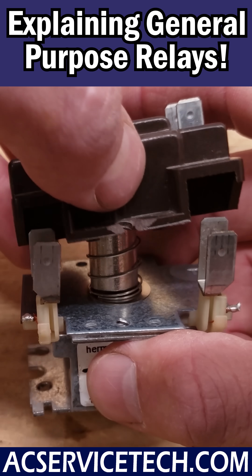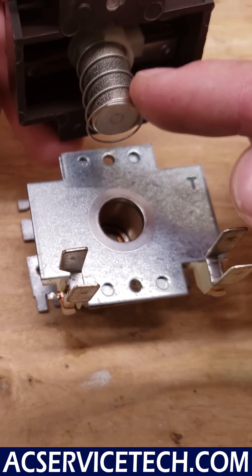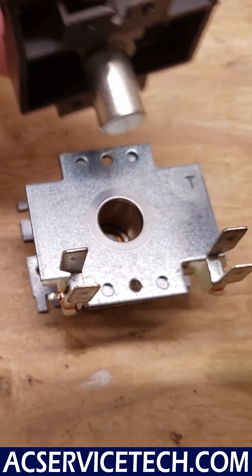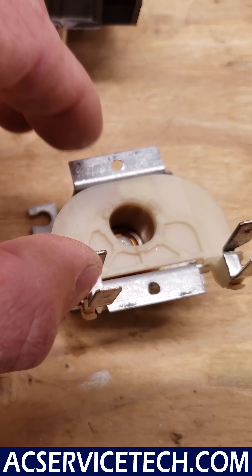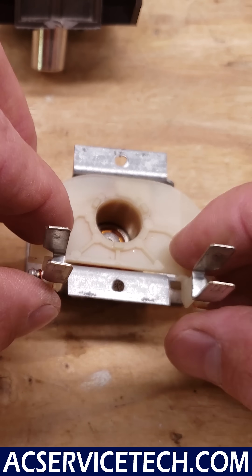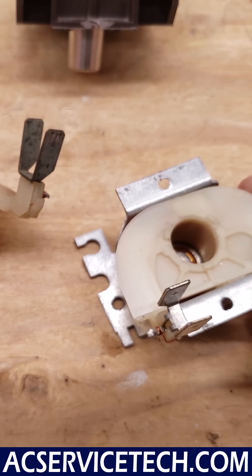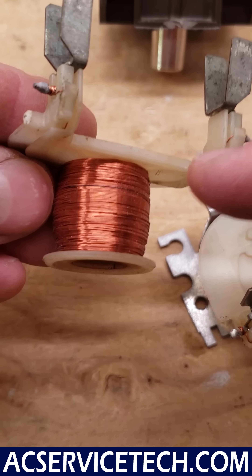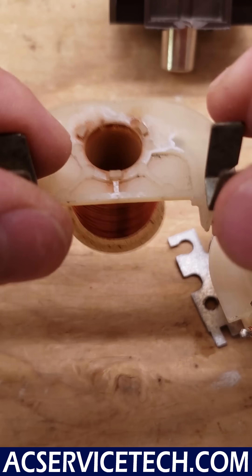I want to take this apart just to show you how this works, but it's pretty simple. You have this spring pushing this iron core in the center upwards, and this iron core is actually sitting down inside this plastic case. So you have the wire wrapped around the plastic case, and on one side of the coil you have these tabs, and it's wrapping around and coming over to this side.